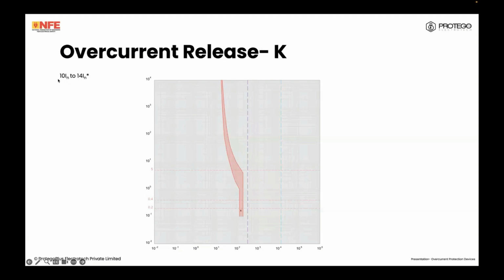Sometimes they're 10 to 14. I've seen 8 to 14 as well. So this is just the general. And there's also the Z here, which is 2 to 3 times. Now there's something interesting you'll notice here: for B MCBs, the same amount of current will cause tripping in basically instantaneous 0.1 seconds.